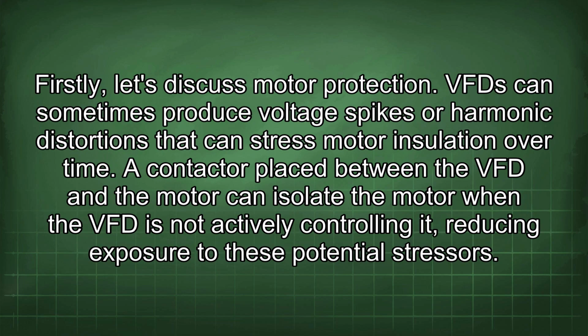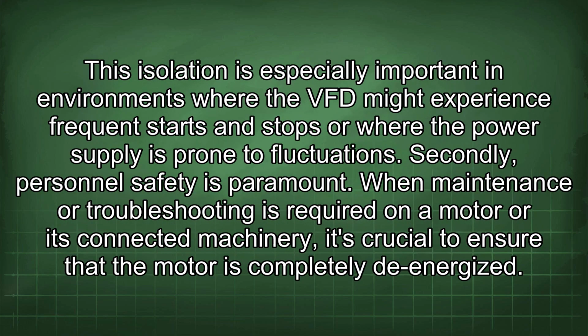Firstly, let's discuss motor protection. VFD can sometimes produce voltage spikes or harmonic distortions that can stress motor insulation over time. A contactor placed between the VFD and the motor can isolate the motor when the VFD is not actively controlling it, reducing exposure to these potential stresses. This isolation is especially important in environments where the VFD might experience frequent starts and stops or where the power supply is prone to fluctuations.